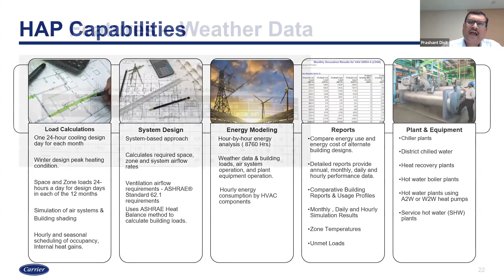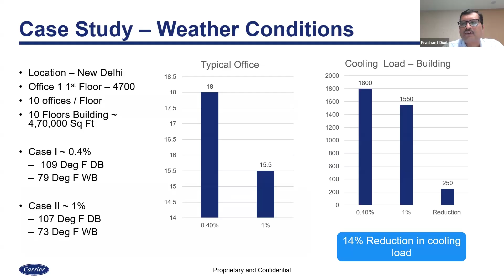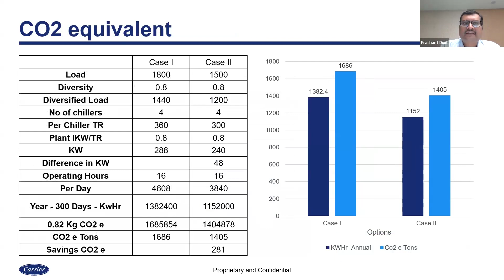I've put one small case study. We took a small office space of 4,700 square feet, very small, like 10 offices in a 10-story building. In case one, considering weather, I took 0.4% and 1% scenarios. With 0.4%, I got a load of around 18 tons, and with 1% weather consideration, around 15 tons. How much did that translate to? 1,800 for one case and 1,550 for another. This means that putting all the factors in this table, I was able to save close to about 281 tons of CO2 equivalent. That's the power of using software-based solutions.